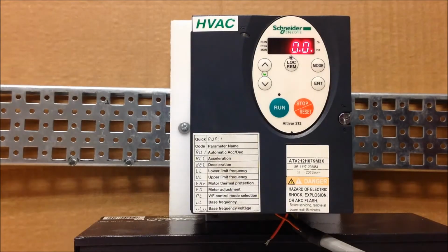This video will show you how to program reference switching functionality on the ATV212 drive. Now, when we're talking about reference switching, we're talking about the switching of your reference channels, meaning your speed channels, not your command. Your command is going to still stay the same as whatever that CMOD parameter is programmed as, which is your command mode selection. But this is strictly a reference switching in means of a speed reference.